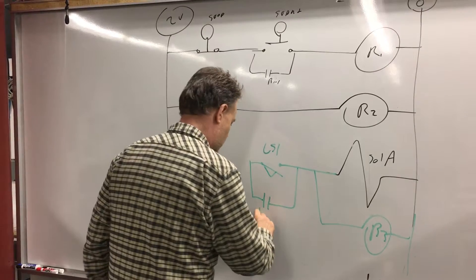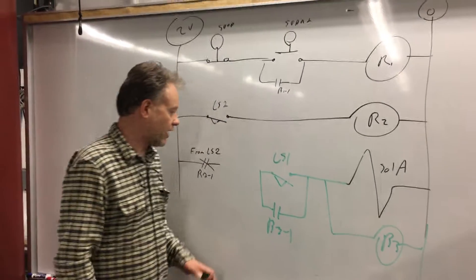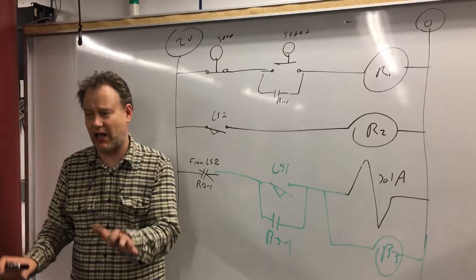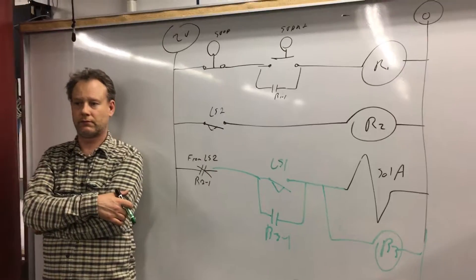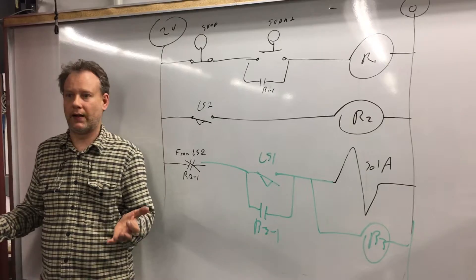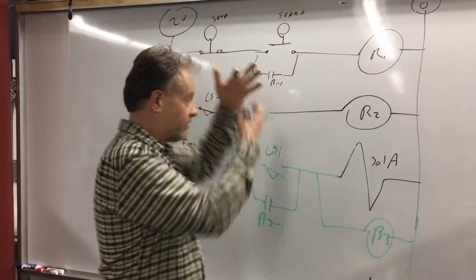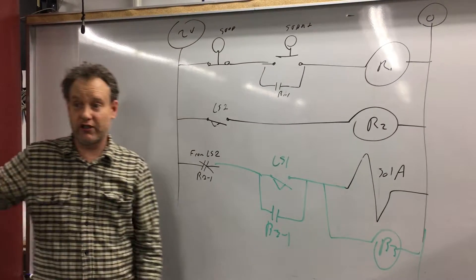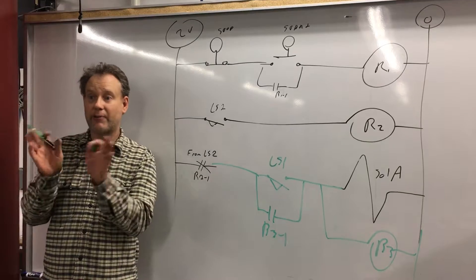We add another relay so that we can have a memory latch remembering that that event happened. I'm going to label it R3-1. Now let's analyze it. If I press start, what's going to happen? Nothing — because R3-1 isn't in here anywhere. That's not very good programming, because as soon as I plug it in, something's going to start to happen and we don't know what yet.